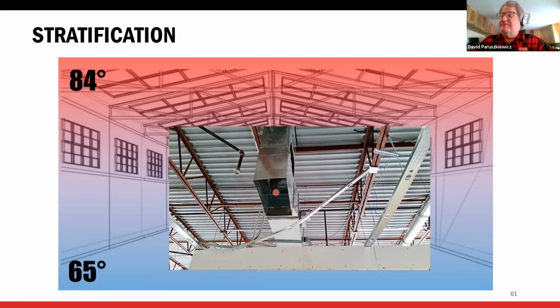Stratification is a big cause of that when the drop from the curb is really short. I've been to ones recently where there's no drop and the supply ducts are a couple feet below the return. All that heat's just going right up the return. So that's something else we should be checking, that return air temperature. If we start approaching 80 degrees or higher, we have to address that because we're going to trip the limit.